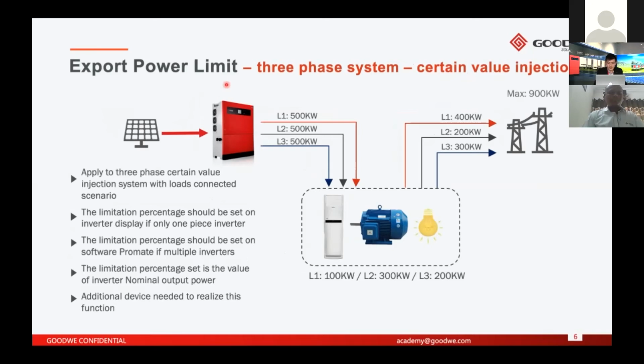And in this case, it's different from the last one. This one you can set a certain value to the grid. For example, here you can set the maximum to 900 kilowatt to the grid. So we also take this as a sample. The load consumption is totally 600 kilowatt, and also 900 kilowatt can go to the grid.